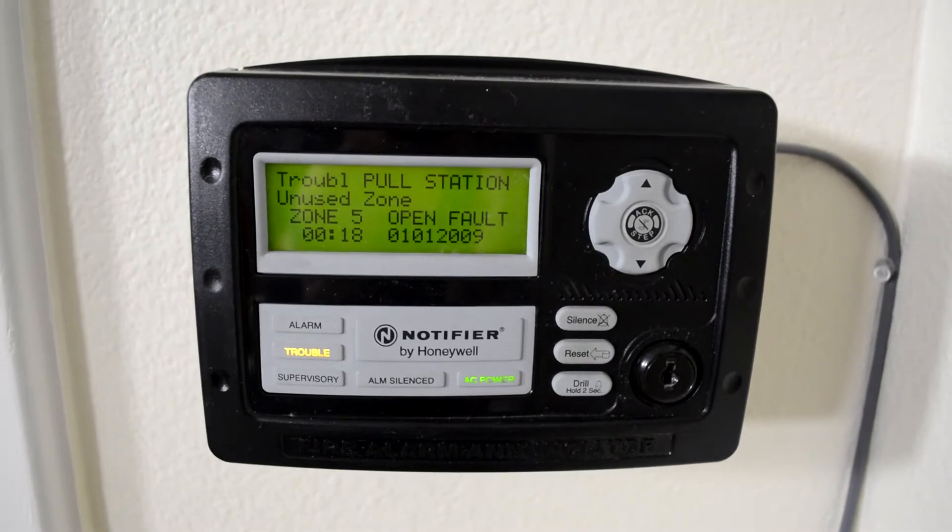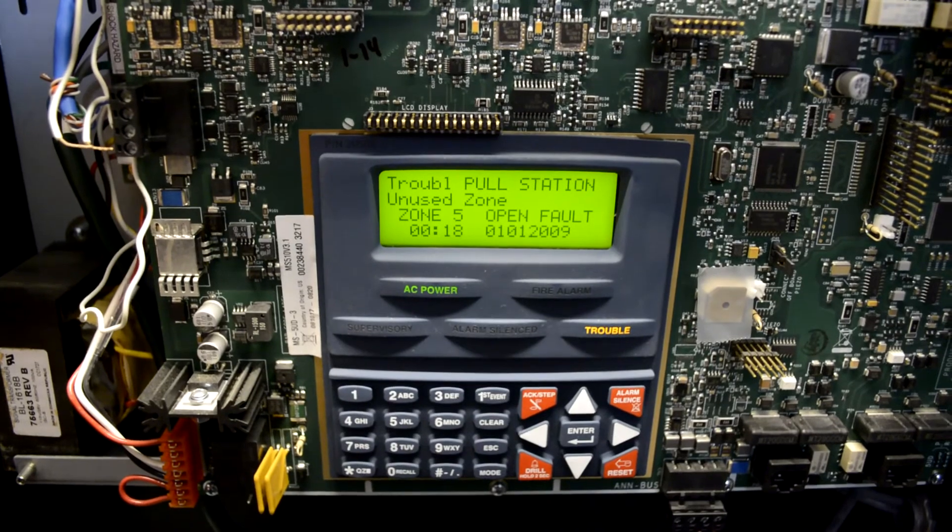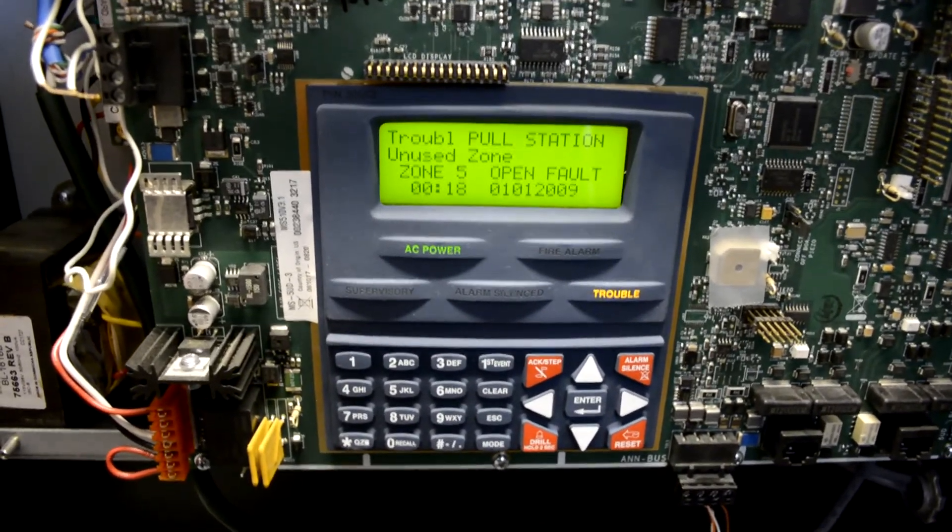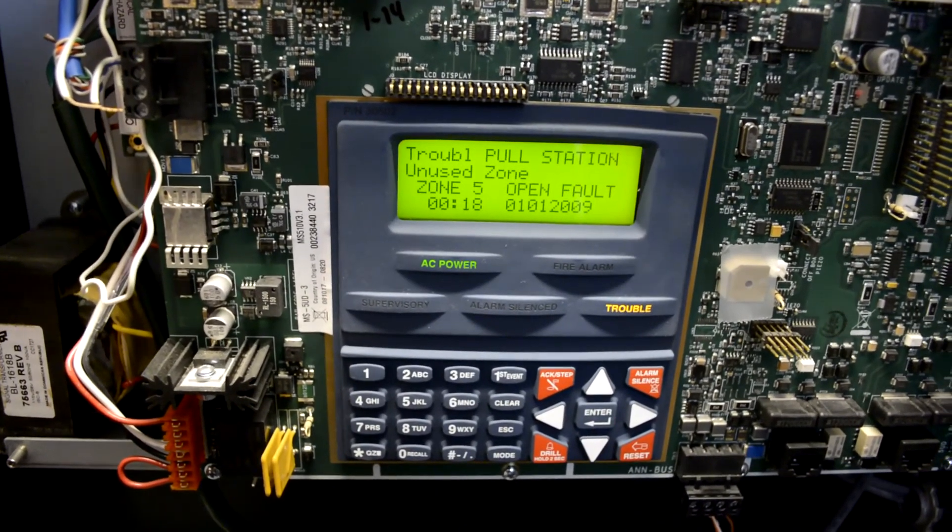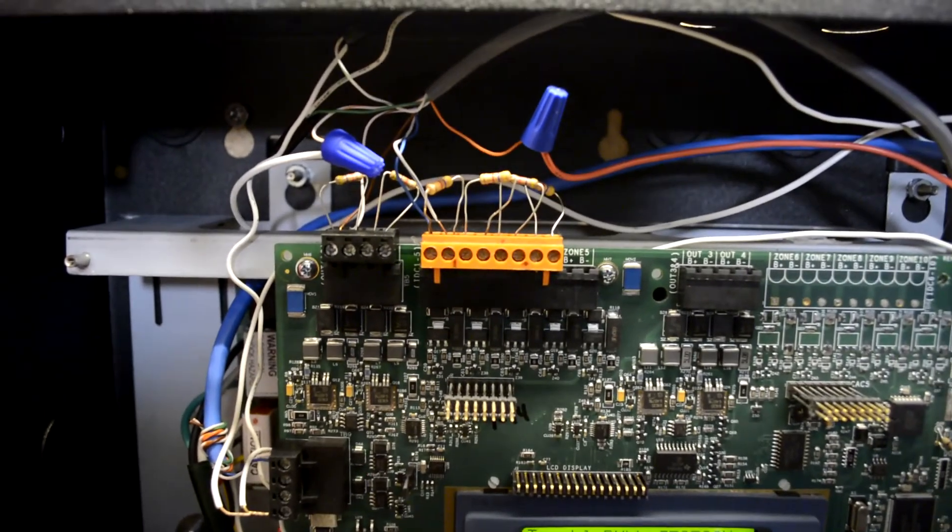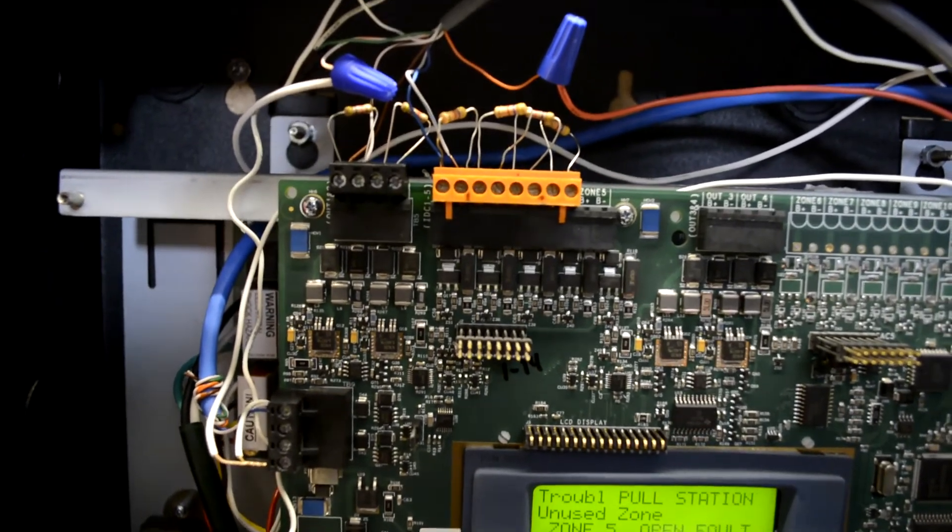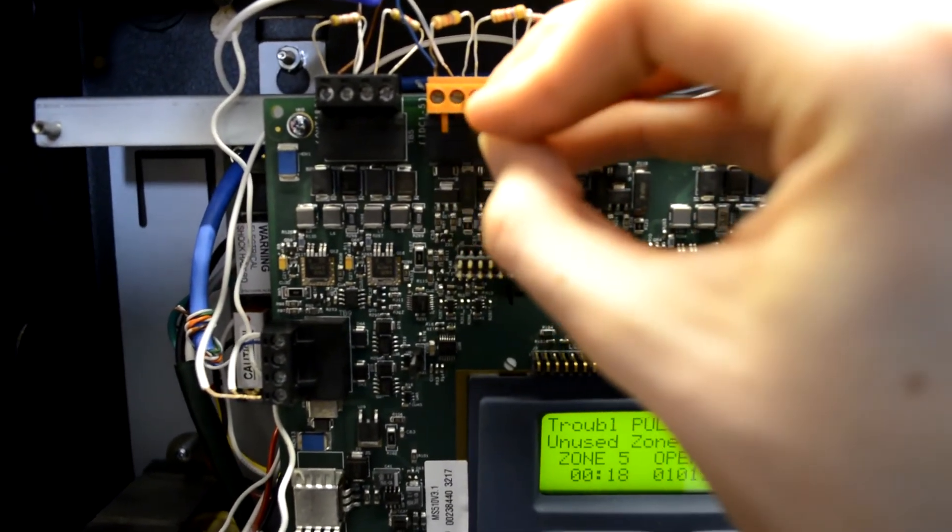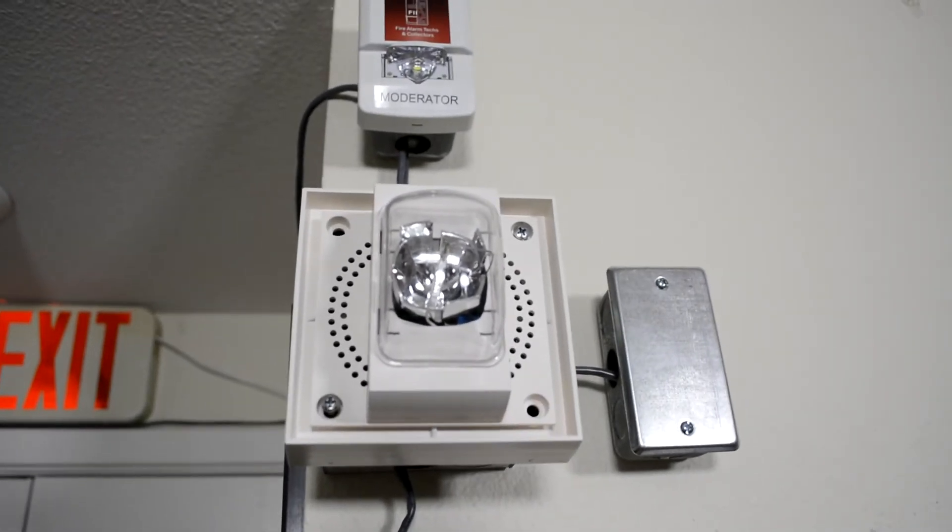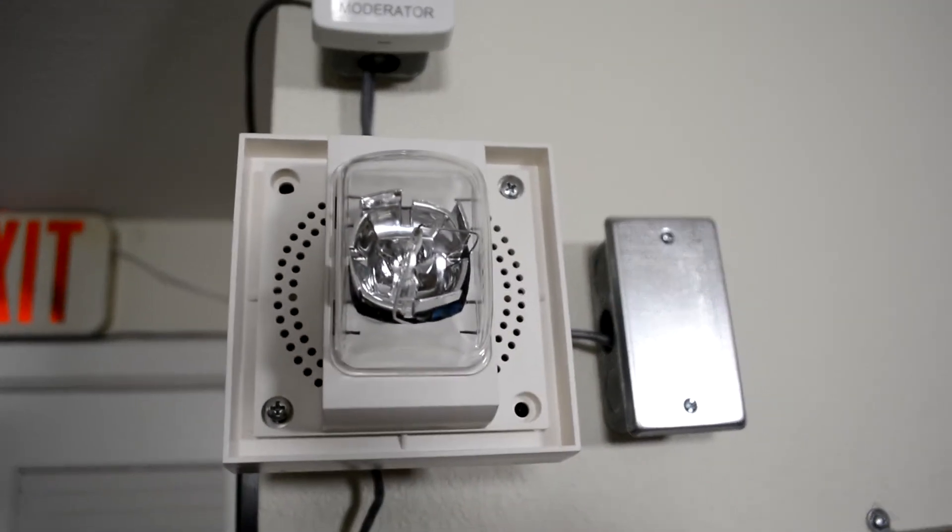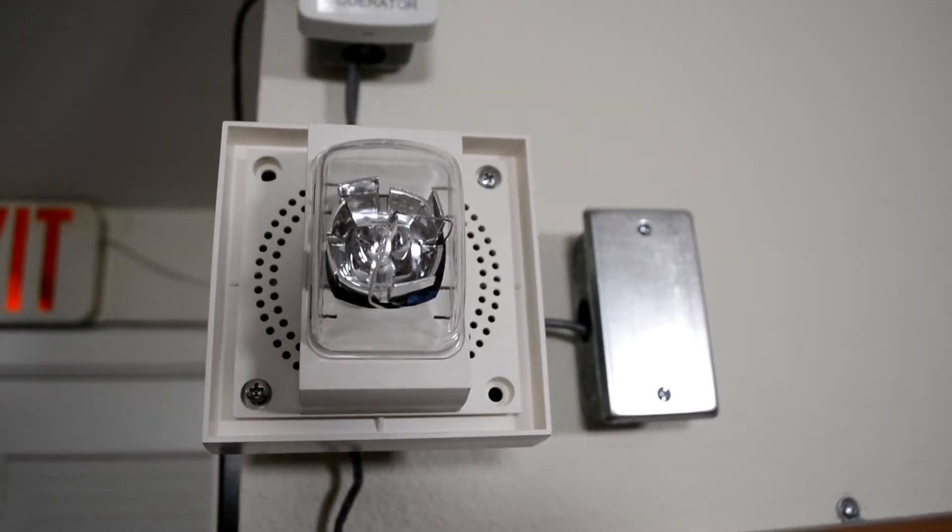For the all clear message, it's going to be coordinated with relay 2, which is the supervisory. In this case I haven't specifically set anything up, so I'm just going to be reusing the moderator alarm zone which did trip a supervisory. I'm going to have to do it from the panel here. This is not something I recommend doing, it's not necessarily the greatest thing to do in the world. I'm just going to jump the zone here. May I have your attention please. The building emergency has ended and all clear has been given. Please resume normal activities. May I have your attention please. The building emergency has ended and all clear has been given. Please resume normal activities.